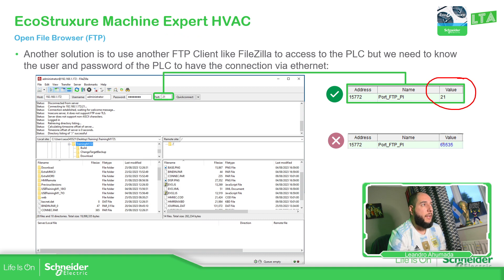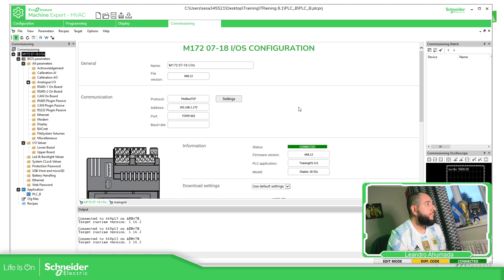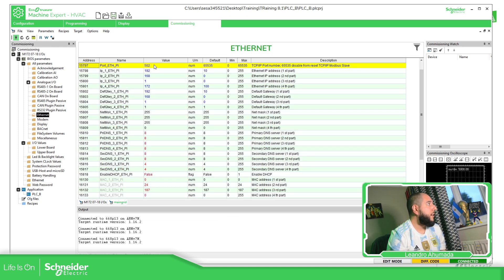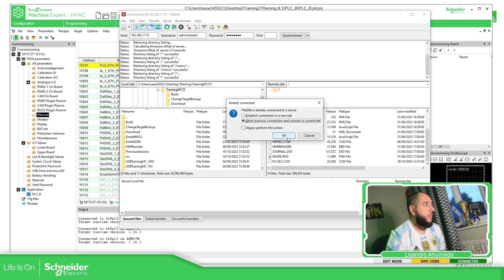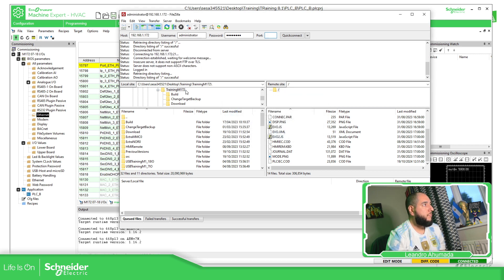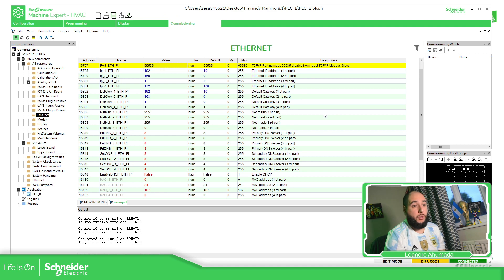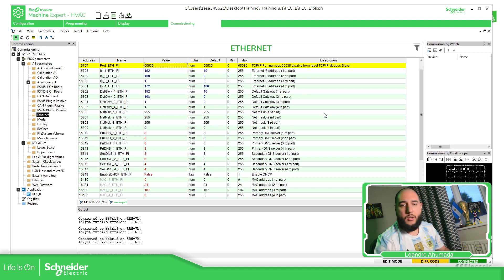This is what I wanted to show you. This is possible because we have FTP enabled. But what happens if we disable it? So I'm going to connect with the controller. Now I'm going to go to Ethernet and set 65535 to disable it. I'm not 100% sure if I need to power cycle it, but let's try to connect again on port 21. It doesn't connect, so we need to power cycle the unit.